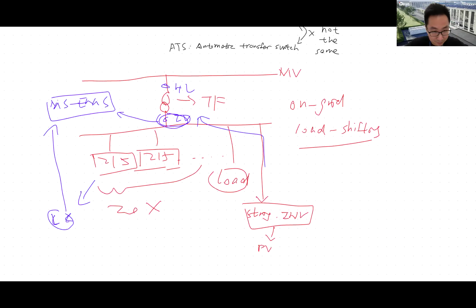If you have a requirement for anti-backfeeding, so you are not allowed to sell anything back to the grid, the EMS will take measurements at your grid access point. Say your string inverter is injecting too much power into your grid, like it's making too much power, and the direction of the power flow is starting to change. The EMS will tell our 215 to start absorbing as much as possible to absorb all of this excess power into our battery. That's one of the functions we have for the EMS.